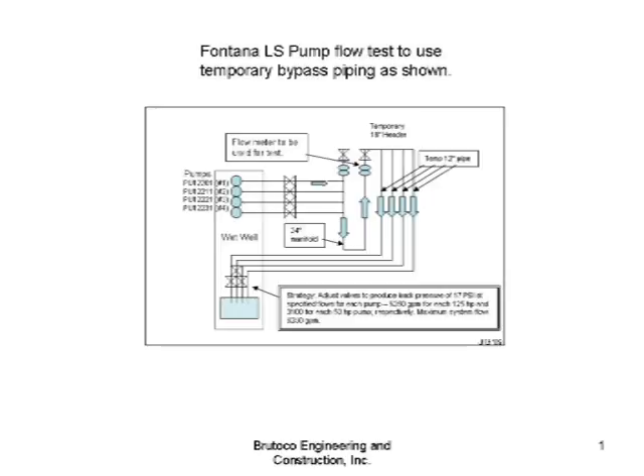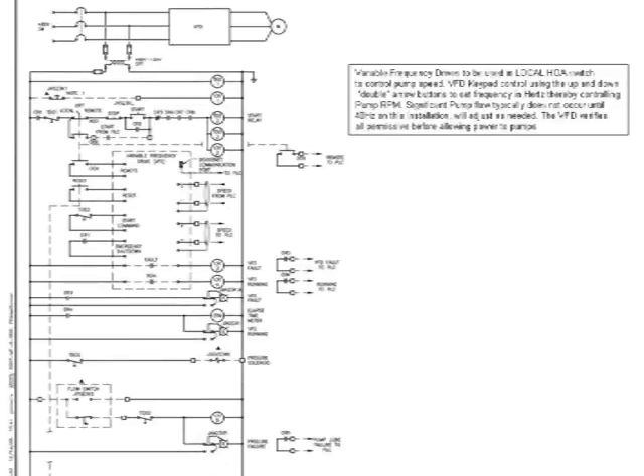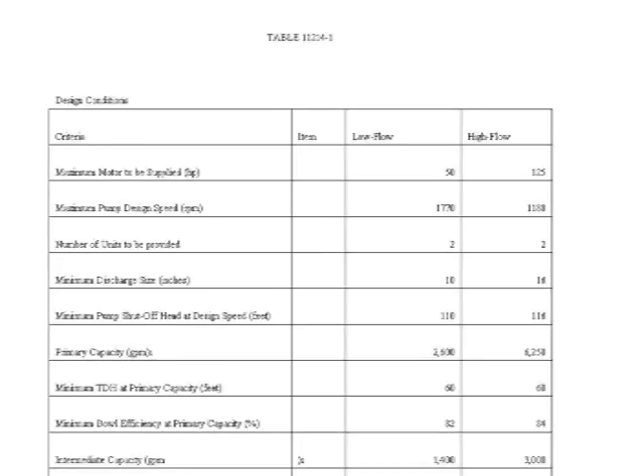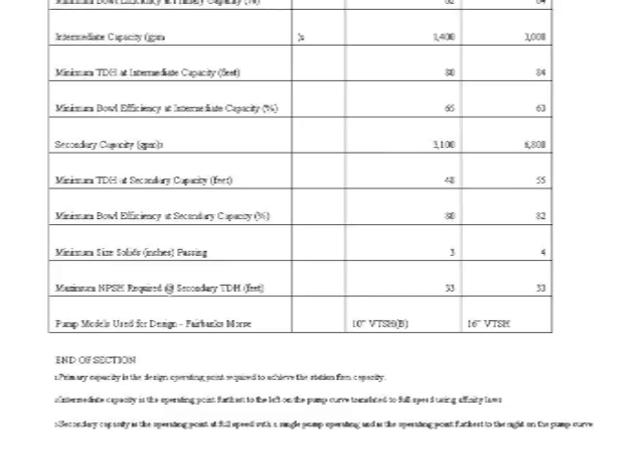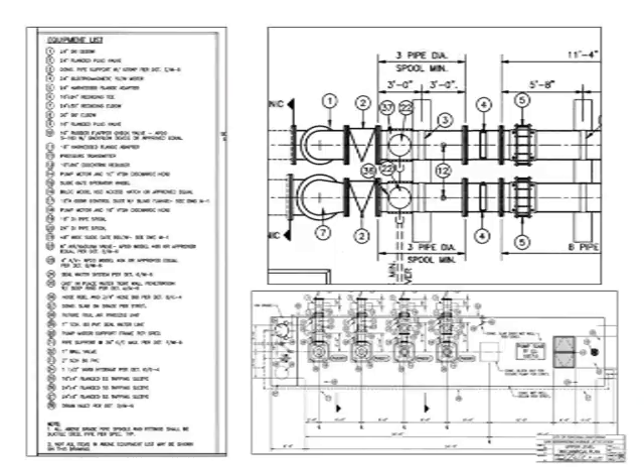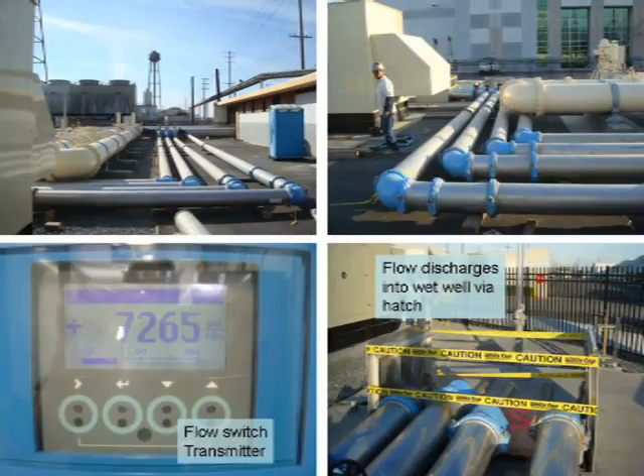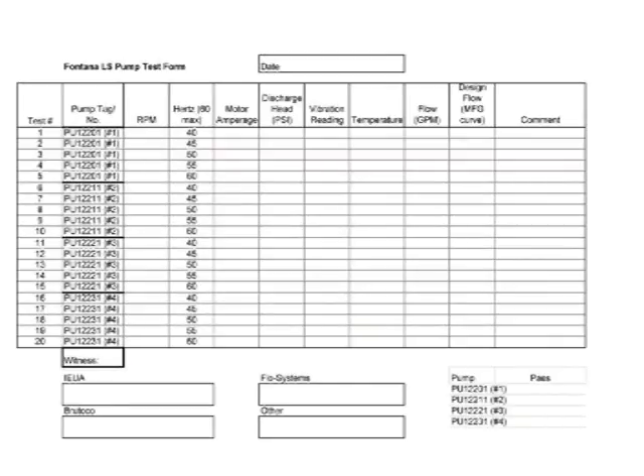Documentation of startup for Fontana Lift Station, which is primarily focused on verifying pump flows for the station. You see a layout here showing how we're going to recirculate potable water from the wet well back into the wet well from the pumps. Flow criteria is listed here, showing low range and high range, what should be expected in GPM performance of each of the pumps. This is a schematic of the mechanical aspects of it, and here's a layout as seen, photographs, except we have a flow meter instead of a flow switch.